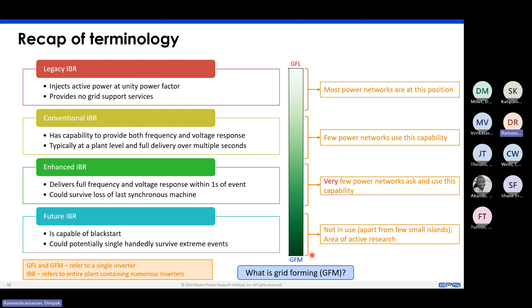If you have something in the subtransient time scale, you can say that grid following is more like a PQ bus in your power flow scenario, versus grid forming is more like a PV bus or a VF bus. In the transient time scale, you can do both active or reactive power control, or voltage frequency control. And toward steady state, you can actually follow similar droop characteristics in both devices.